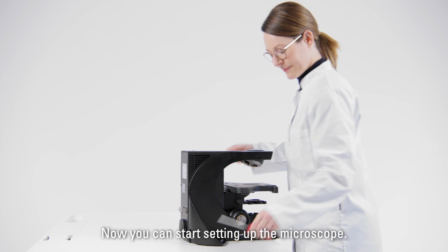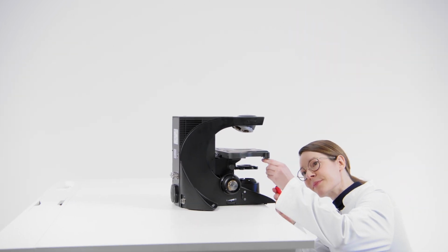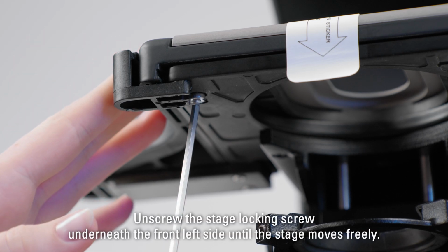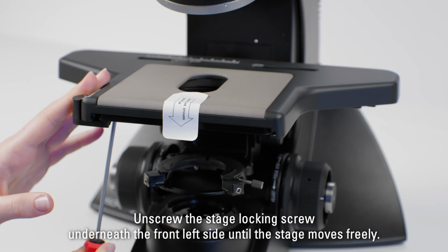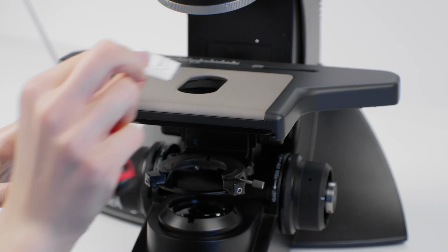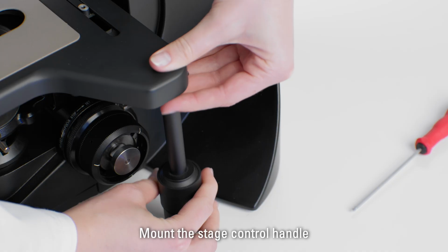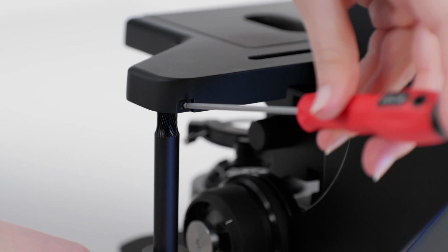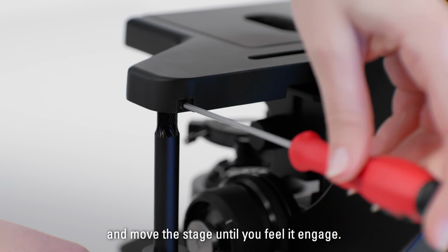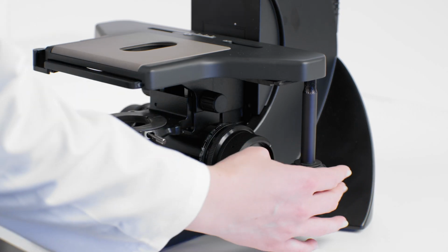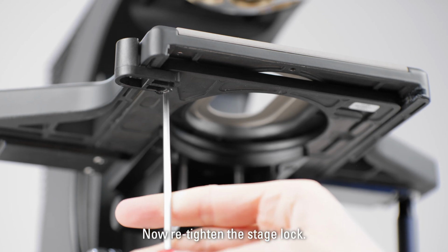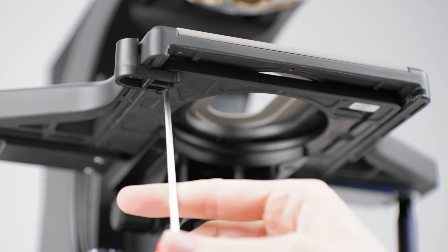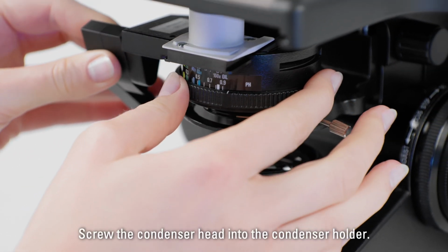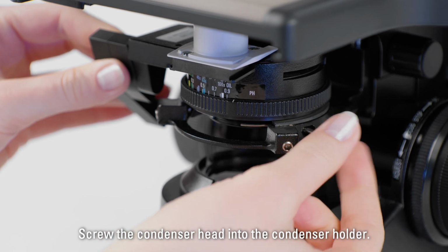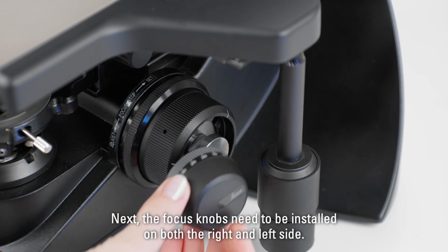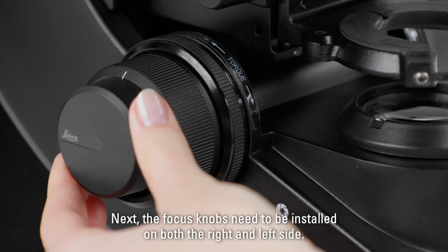Now you can start setting up the microscope. Unscrew the stage locking screw underneath the front left side until the stage moves freely. Mount the stage control handle and move the stage until you feel it engage. Now retighten the stage lock. Screw the condenser head into the condenser holder. Next, the focus knobs need to be installed on both the right and left side.